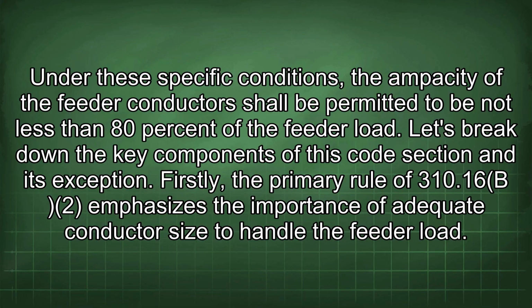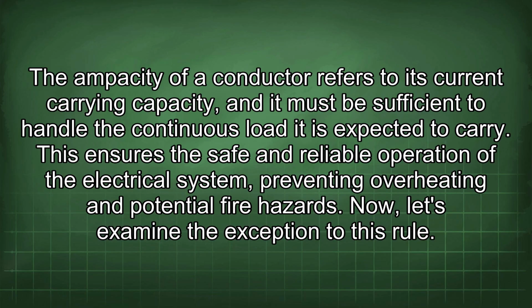Firstly, the primary rule of 310.16b2 emphasizes the importance of adequate conductor size to handle the feeder load. The ampacity of a conductor refers to its current carrying capacity, and it must be sufficient to handle the continuous load it is expected to carry. This ensures the safe and reliable operation of the electrical system, preventing overheating and potential fire hazards.